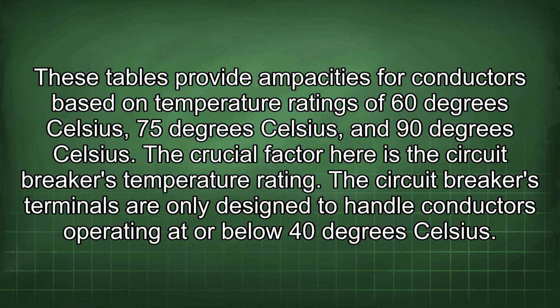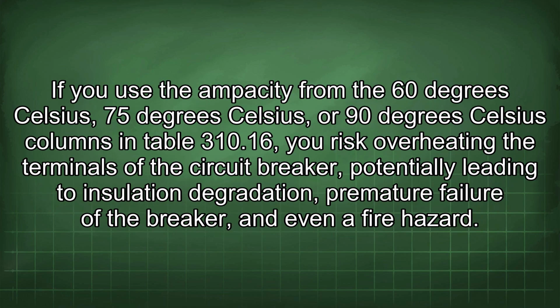The circuit breaker's terminals are only designed to handle conductors operating at or below 40 degrees Celsius. If you use the ampacity from the 60 degrees Celsius, 75 degrees Celsius, or 90 degrees Celsius columns in Table 310.16, you risk overheating the terminals of the circuit breaker, potentially leading to insulation degradation, premature failure of the breaker, and even a fire hazard.